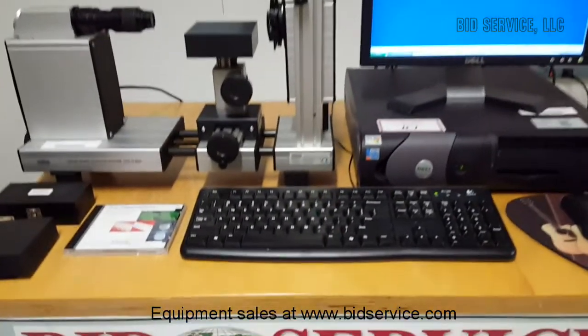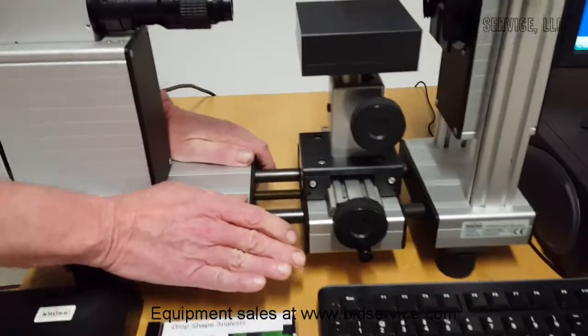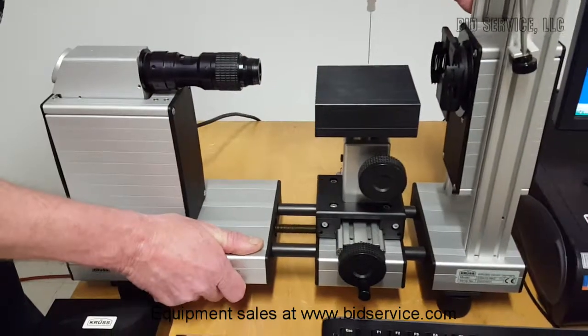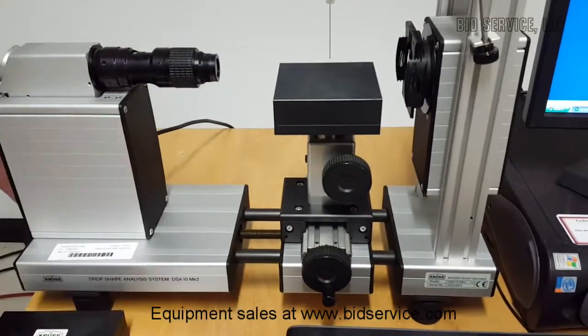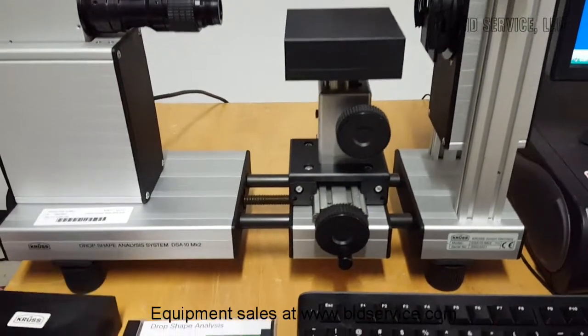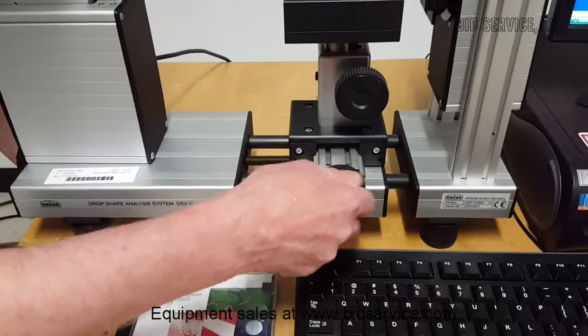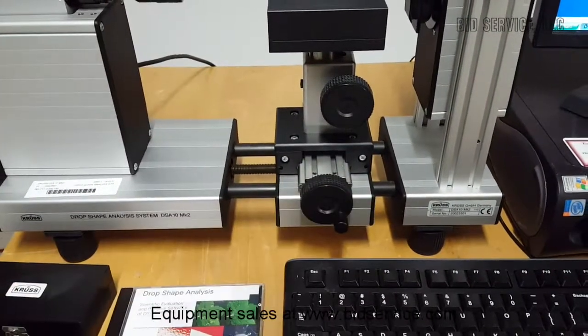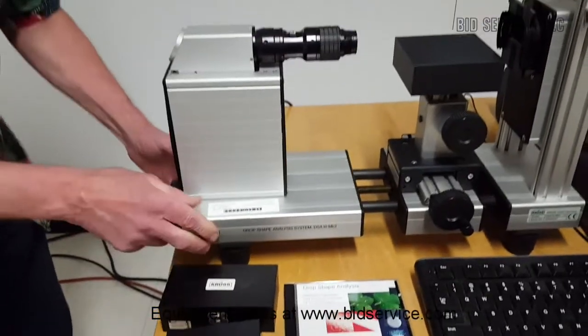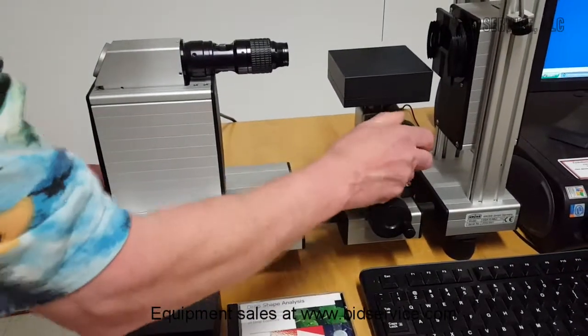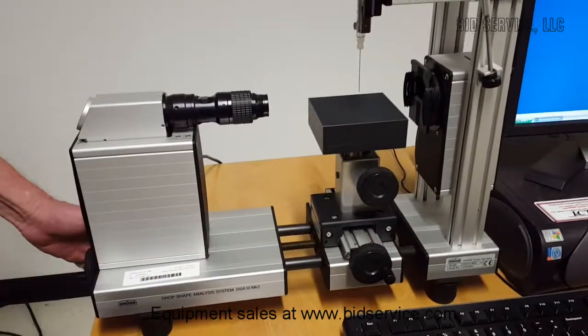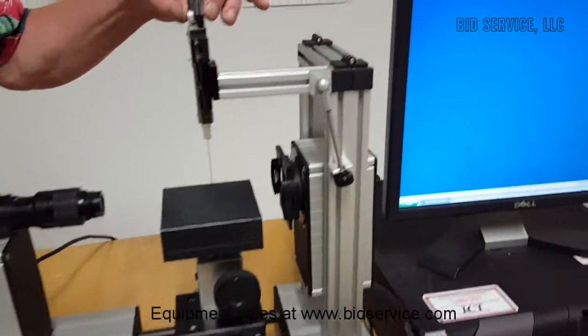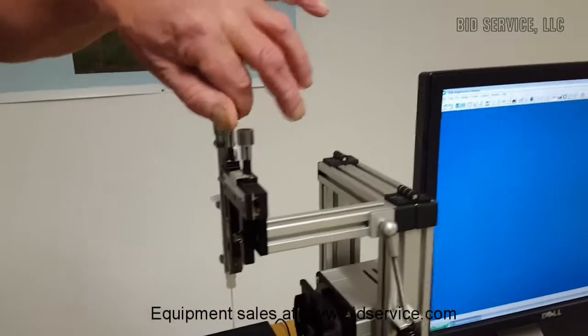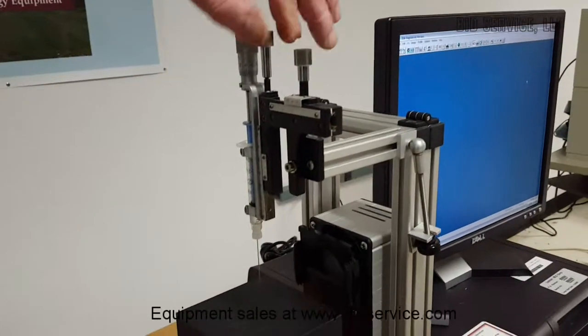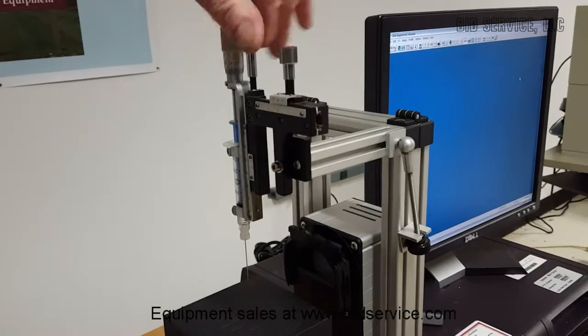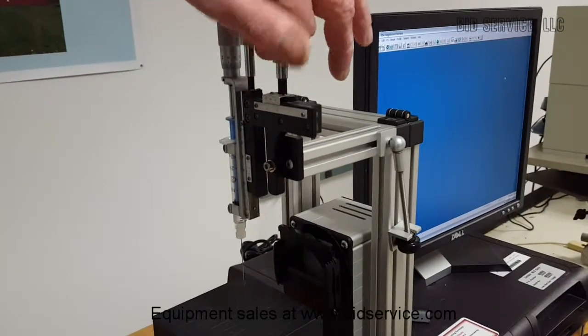Let me first point out some of the features of our measurement bench here. Very lightweight, yet at the same time, it's got just enough weight so it's pretty much vibration free. It has individual leveling feet on the bottom as well. This would be your Y travel, this would be your X travel, and of course this would be your Z travel up and down. In addition, we have a manual holder here where we have both Z motion to bring your needle down close to your base, and we have a Y motion back and forth as well.